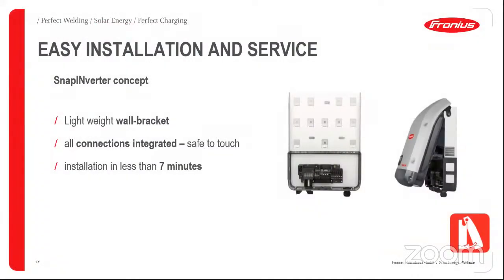So as you see in the last video, to start the operation of the inverter is very simple. We just need to locate the wall bracket and then close the electronic side of the inverter, open the DC switch, and that's it. After we connect DC and AC cabling, the inverter will start the synchronization of the grid, and then it starts producing energy. So it's very simple, it's very easy, it doesn't take a lot of time. And also the commissioning and the communication to our internet only needs a couple of steps and it's very fast and easy to do.